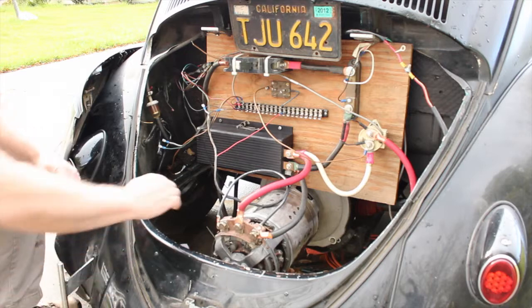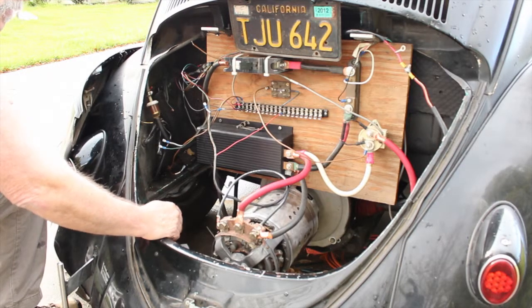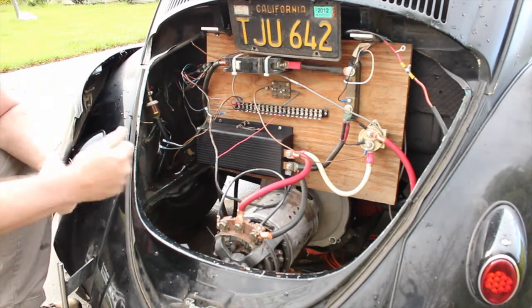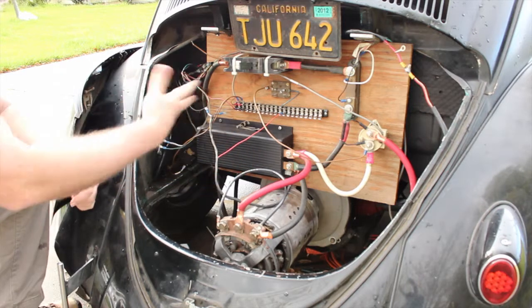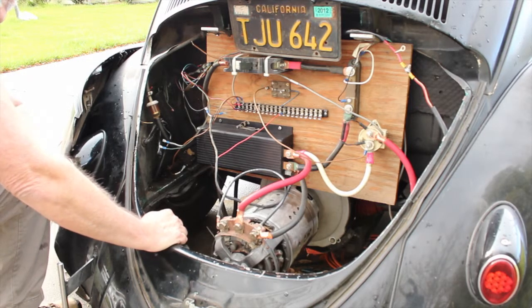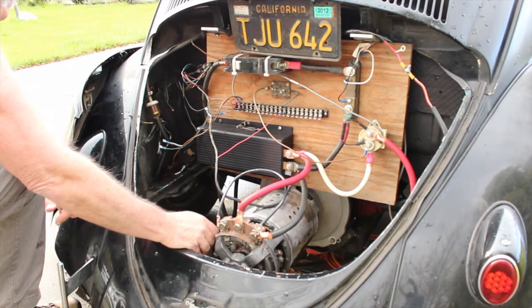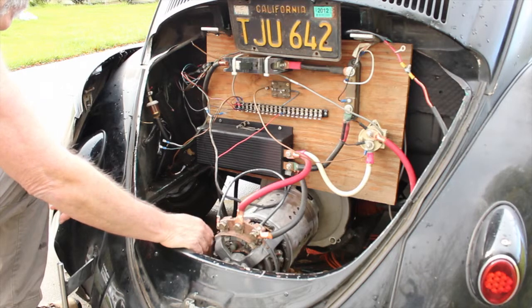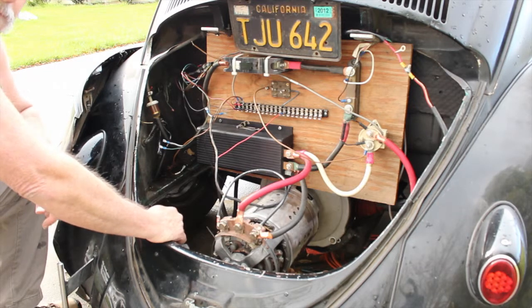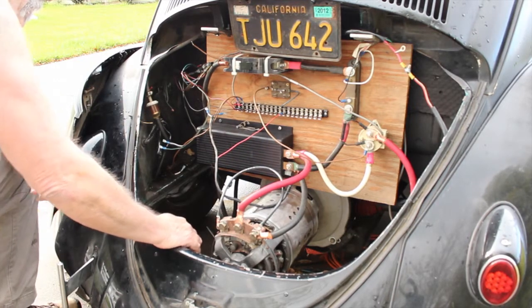Running the motor just unloaded like that, the way I have it shunted, the motor is really hot too. So shunting the motor and running it off a series-style controller is not going to work — you're going to overheat things real fast. You would seriously overheat this motor and the controller, and I don't know if you could even cool it off fast enough. A shunt motor needs a shunt controller or separately excited with low voltage, and be done with it.